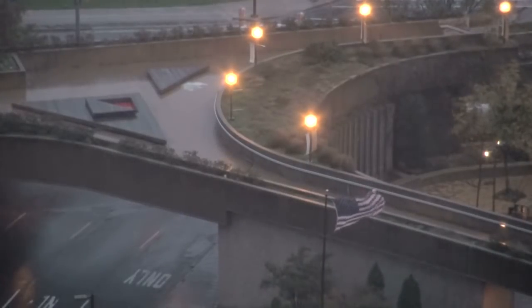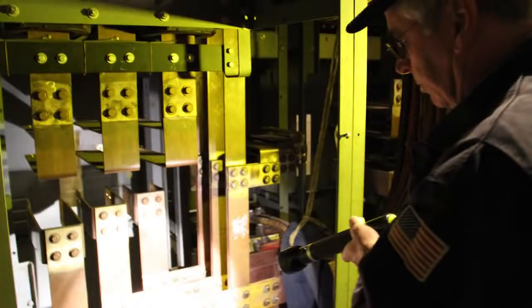Here I am standing at Pier 40 in Manhattan, in the main electrical room of the New York State Parks Commission. We have a pair of 4,000 amp switches that feed transformers and then 480 volt distribution equipment behind me. When Sandy came in, there was about 3.5 feet of water in this room. The bus bar went underwater and the transformers failed.